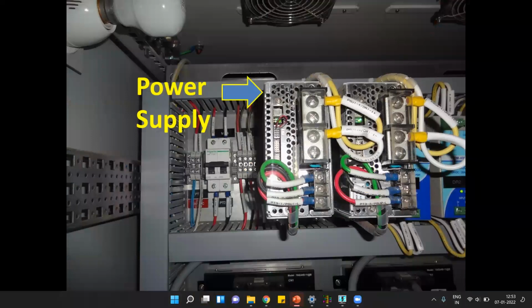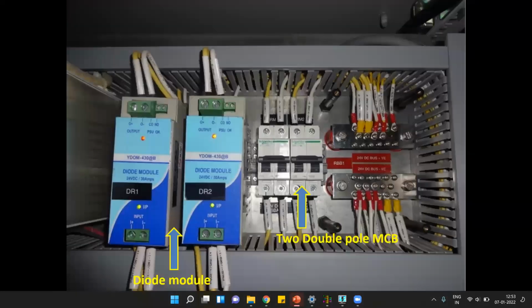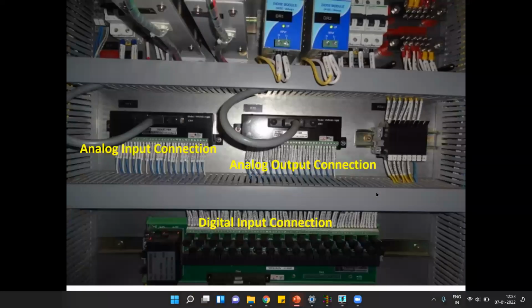And if the power of one supply is working, then there is a diode after both power supplies, so that the power of one power supply cannot interfere, means cannot go to the other power supply. It will directly go to the bus line. This is the bus line. And from this bus line we can get a 24 volt supply.